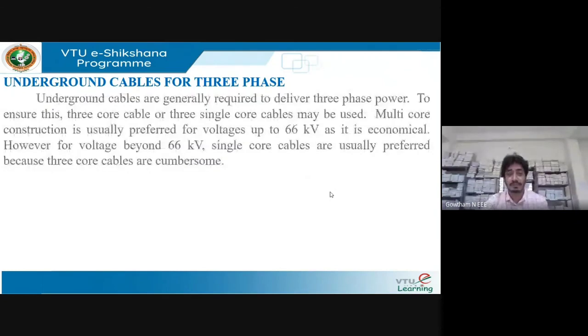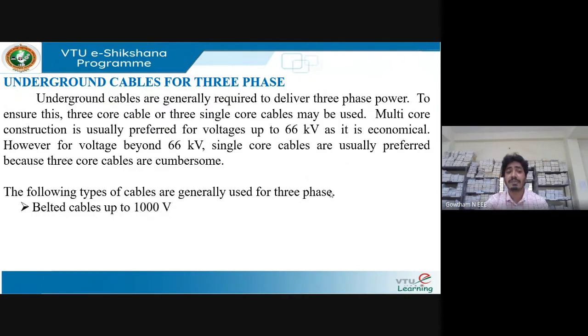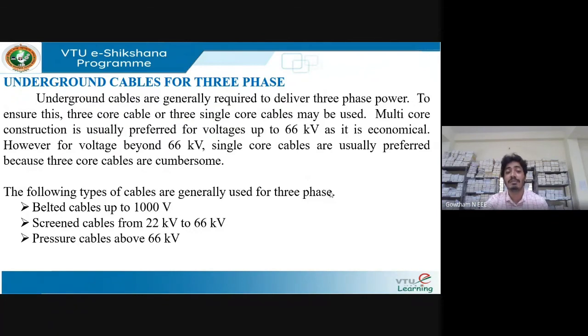For three-phase underground cables, the construction must be robust. Multi-core construction is preferred for voltages up to 66 kV as it is economical. For voltages beyond 66 kV, single core cables are preferred because three-core cables are more complex and mechanical/maintenance costs are very high. Types of three-phase cables include belted cables operating up to 1000 volts, screened cables for 22 kV to 66 kV, and pressure cables for above 66 kV.